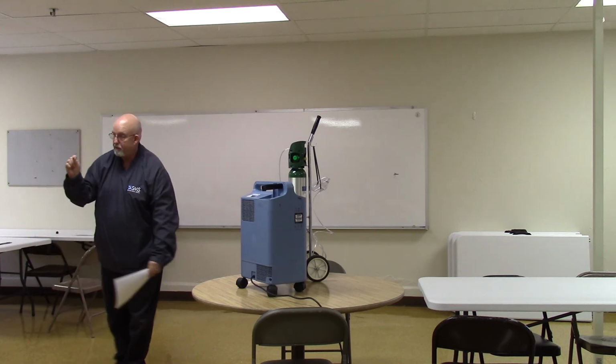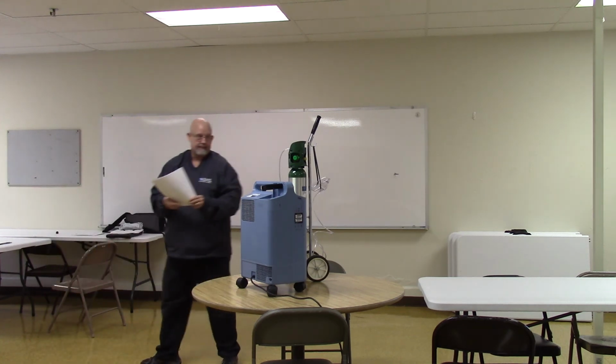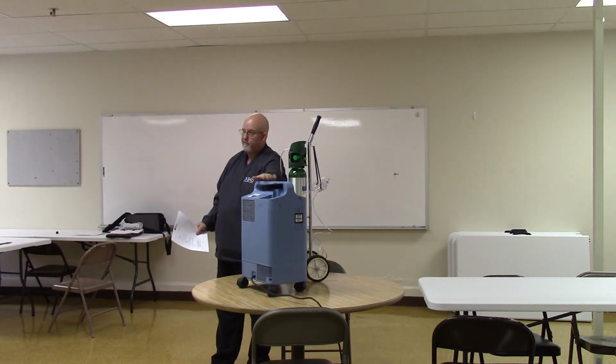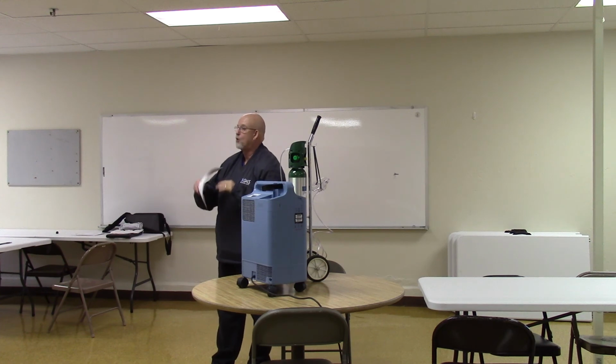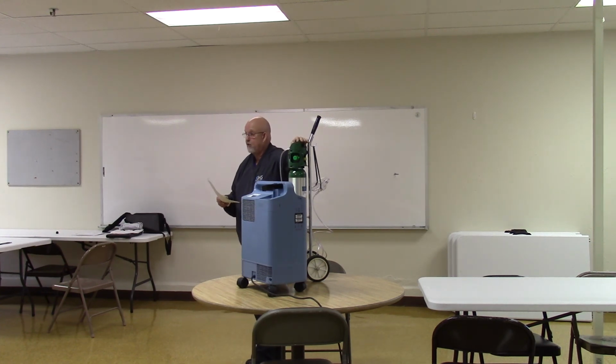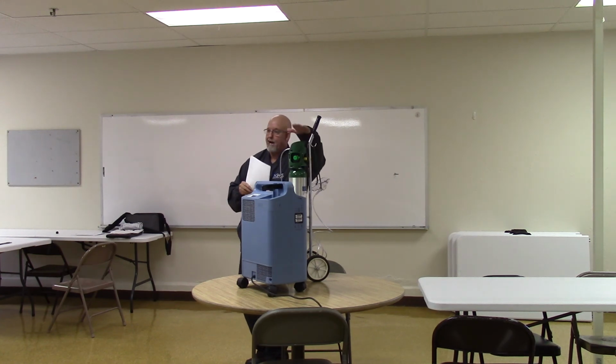In the emergency part of what we're talking about, grab this. This, or even the 10-liter concentrator, can't help you because we can't go above it. This can, okay? It'll go to 15 liters. In an emergency, grab this and your non-rebreather mask.